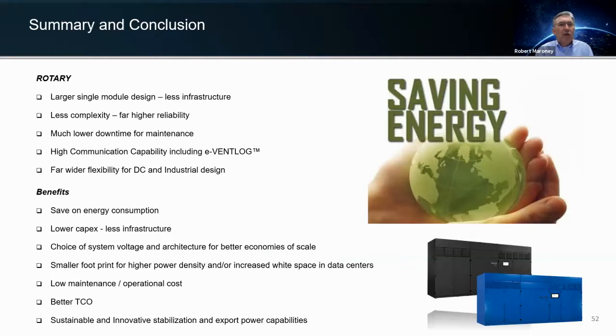So, summary and conclusion: rotary, large-scale single module systems with less infrastructure, much lower downtime. More flexibility for the data center and industrial sectors for the clients. More efficient, save energy, lower CapEx, and a choice of voltage systems. One of the nice things about this is we can do your voltage, whether it's 480 volt or 1247, 4160, 15 kV. It doesn't matter what your voltage is, we can accomplish that for you.